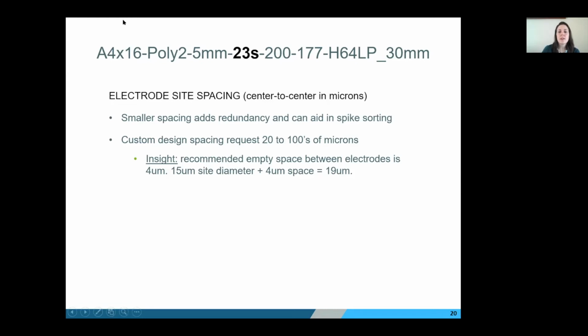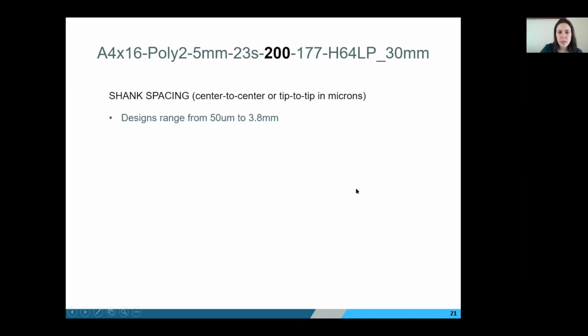You can think of these, again, it's center to center spacing. Our typical sites are a 15 micron diameter circle, and usually we say the empty space where there's no electrode is about 4 microns. It's tiny, but it's far enough apart that they're not running into each other. So if you add that 15 and that 4, that's 19 microns. So a nice round number, we say the smallest site spacing would be 20 microns.